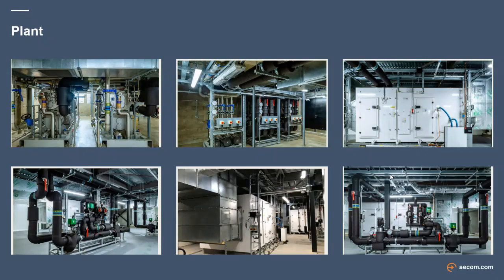The ventilation system consisted of three air handling units feeding a common supply header, then a series of secondary low level headers to ensure even distribution of air around each chamber. We modelled the airflow in CFD analysis to confirm the airflow velocity was as expected. The airflow needed to be delivered to between minus 20 and 40 degrees with 0.5 plus or minus accuracy, and control was 5% on the RH as well, so really quite tight limits. The ductwork had to be designed to minimize condensation and icing.